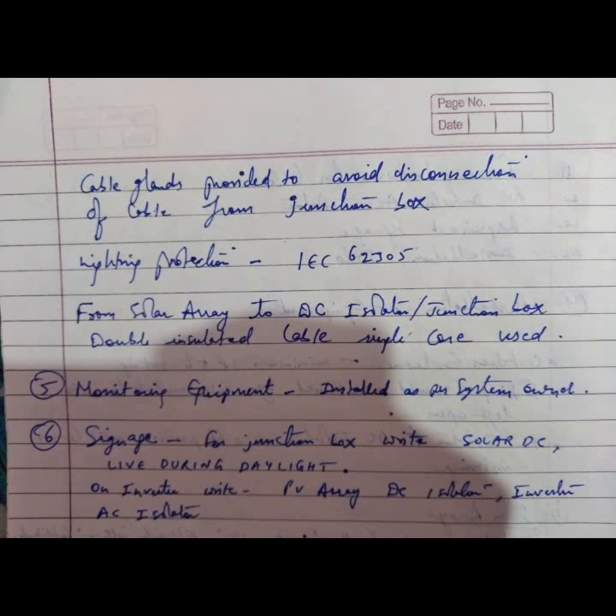Lightning protection: IEC 62305, lightning arresters are there for lightning protection. Solar array to DC isolator junction: double insulated single core cable used. Monitoring equipment installed as per system owner. Signage for junction box: solar DC live during daylight, you can write. On the inverter write PV array DC isolator, inverter AC isolator. So these points you can write on your inverter, and all these points are included in the installation of PV plants.